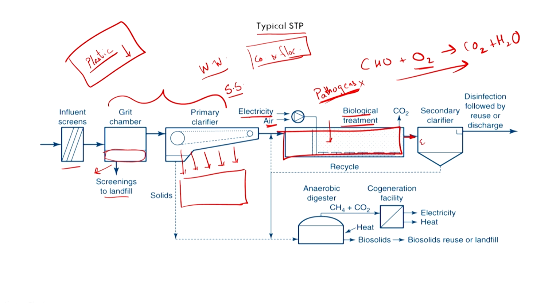And then these microbes, after aeration, are taken to a secondary clarifier. Secondary clarifier means you do not have any mixing, whatever can settle will settle down. So the flocs, the microbes that now form flocs, settle down, and the clear water above is sent out for discharge or disinfection. That is something to keep in mind. But what about this sludge? Again, this is also organic matter, the microbes.